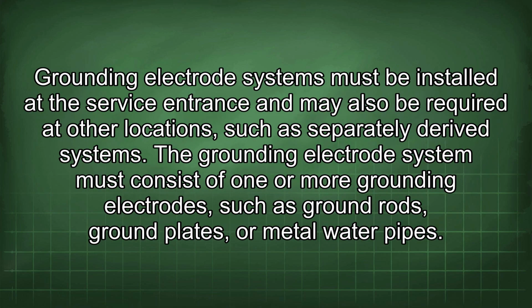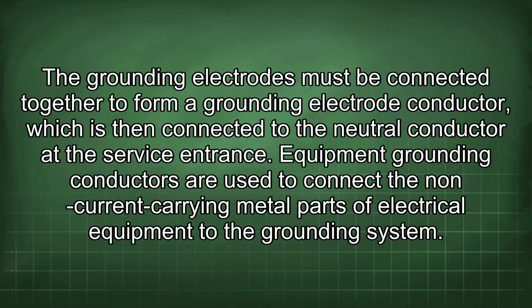Grounding electrode systems must be installed at the service entrance and may also be required at other locations, such as separately derived systems. The grounding electrode system must consist of one or more grounding electrodes, such as ground rods, ground plates, or metal water pipes. The grounding electrodes must be connected together to form a grounding electrode conductor, which is then connected to the neutral conductor at the service entrance.